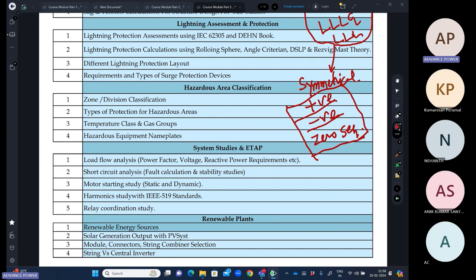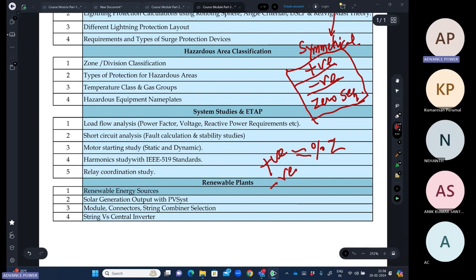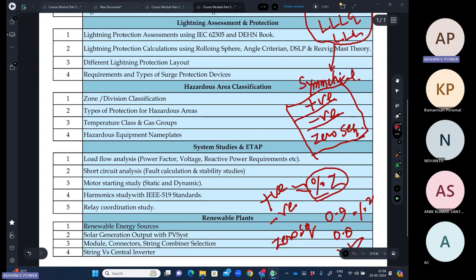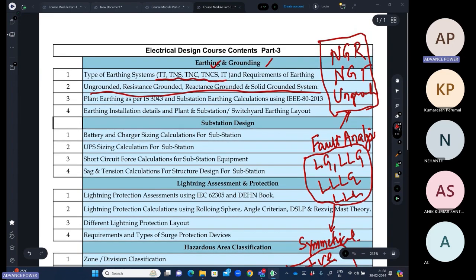Suppose in transformers the percentage impedance is defined. Actually this percentage impedance is the positive sequence impedance, and it is also the negative sequence impedance, which is equal to the percentage Z which we calculate. The manufacturer also mentions the zero sequence impedance of the transformer, sometimes written as 0.8 or 0.9 times the percentage Z, which is the short circuit fault impedance. How it is calculated, we'll draw, we will calculate, we'll study the Thevenin equivalent, and we'll be able to know all these parameters in detail.